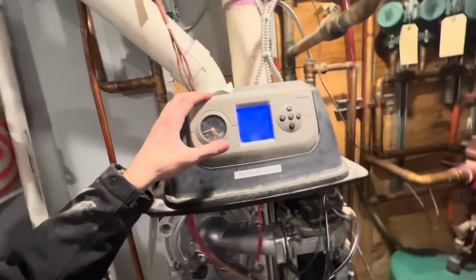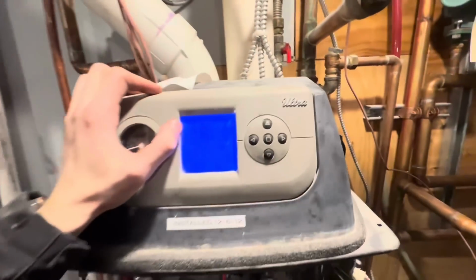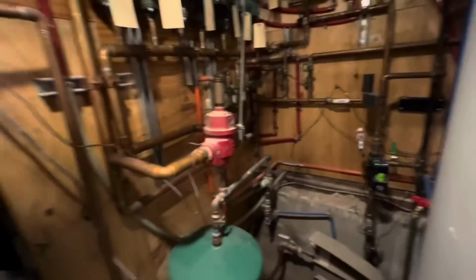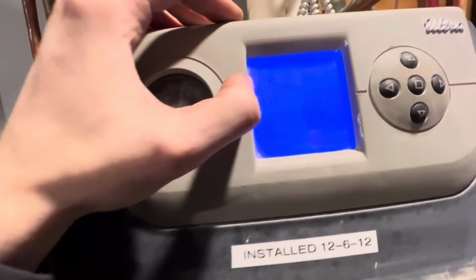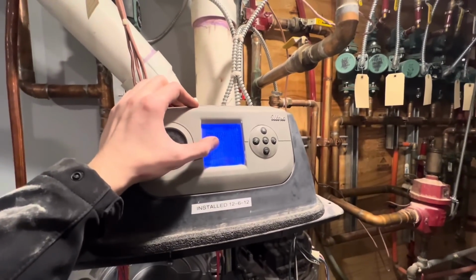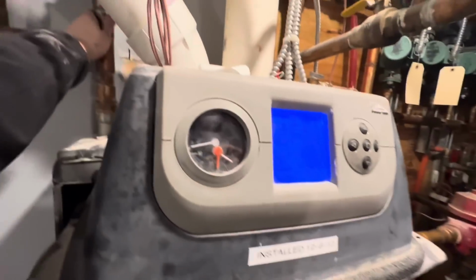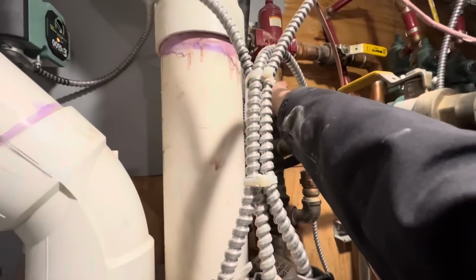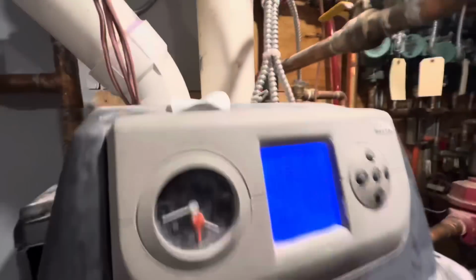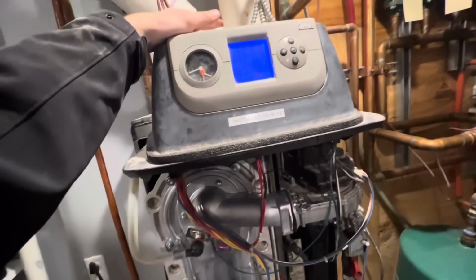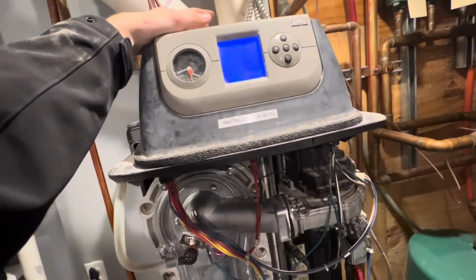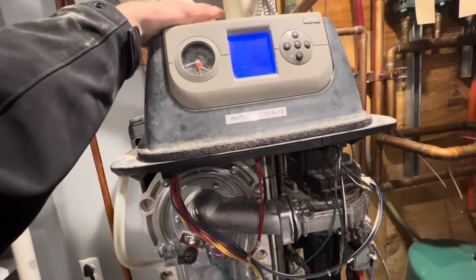Okay, so the boiler's pretty loud because of the blower, but here's our readings. Looks like our supply and our return temperature sensors are reversed, but our boiler out and our boiler in temperatures are okay. We got 135 and 94, so we're returning warm, coming out hot right here. So we got circulation. We'll just make sure that continues to run okay and monitor it.